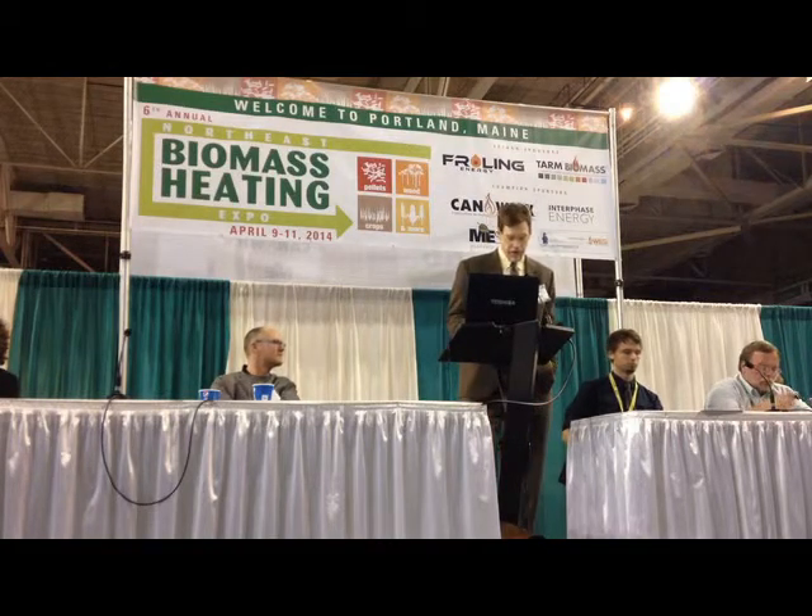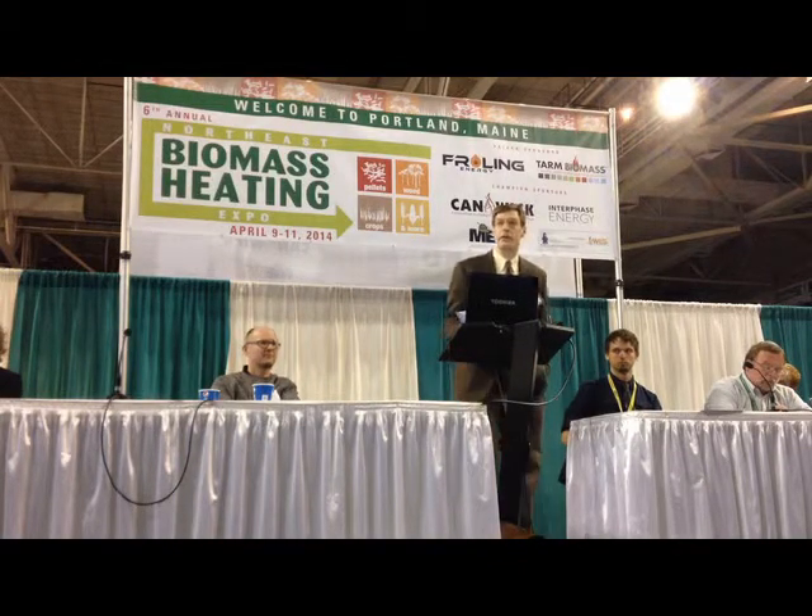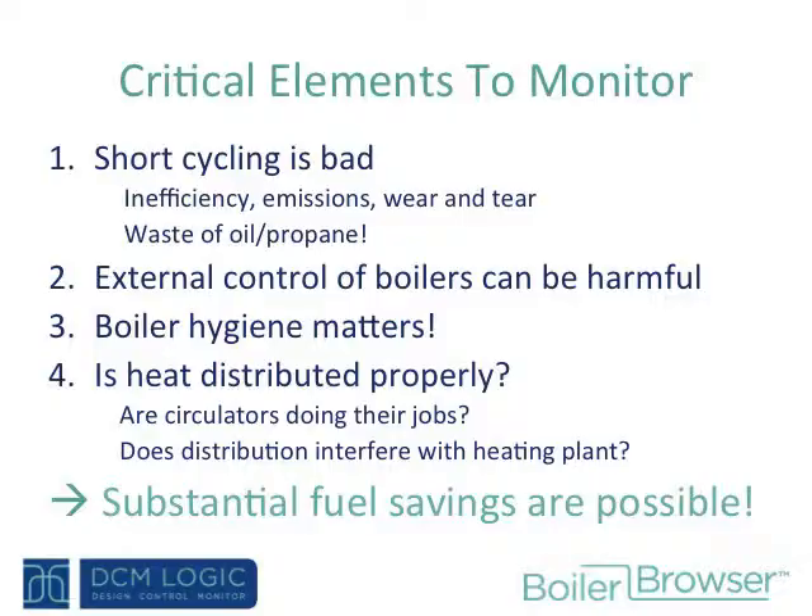Those pictures were just to whet your appetite. Many of you have heard Scott Nichols give a presentation demonstrating the downside of starting up and shutting down a boiler — you light the match and see all the smoke and pollution. But beyond the inefficiency and the pollution, if your boiler is spending all its time starting up and stopping — and in some cases that might take 30 or more minutes — you're going to have a much greater likelihood that your fossil fuel boiler has to come on to make up the shortfall. Do whatever you can to provide nice long run times. One hour per start really stinks; if you can get four or more hours, that's great.